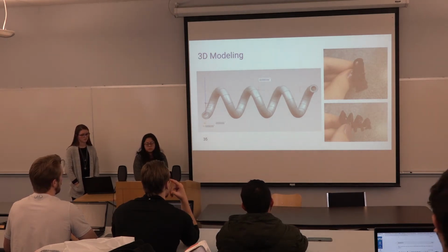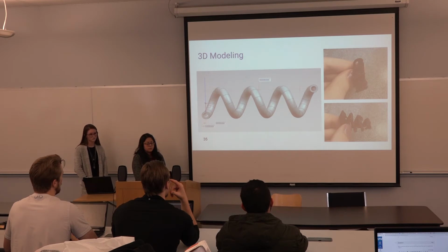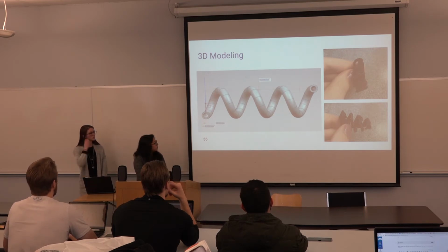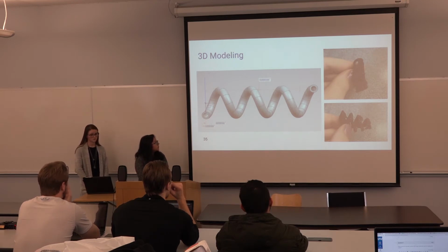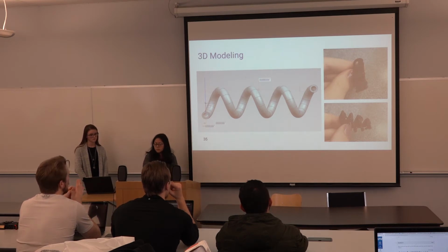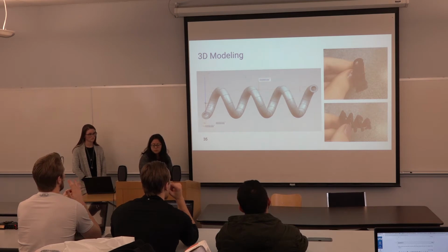Originally, the cuff was designed to be a hollow coil about 35 millimeters in length with a thickness of only 0.5 millimeter. The hollowed area allows for gas or fluid to enter the cuff, expand it, and close the urethra. A lot of current cuff models are actually actuated this way. Unfortunately, the size of the cuff opening prevents this from really being a feasible option.